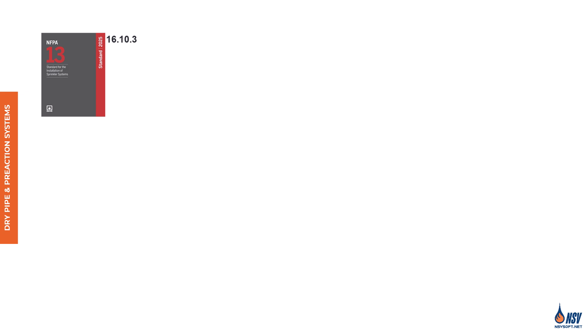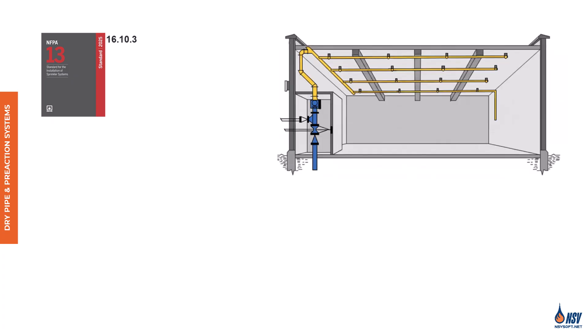Section 16.10.3 of NFPA 13, 2025, outlines the pipe pitch requirements for dry pipe and pre-action sprinkler systems. Proper drainage is essential, especially in areas subject to freezing, to prevent water from accumulating and causing damage. Because these systems are often installed in environments prone to freezing, proper drainage is critical. Water trapped in the pipes can freeze within minutes in areas maintained at or below 40 degrees Fahrenheit. Additionally, stagnant water can lead to internal pipe corrosion and calcium buildup, which may obstruct sprinkler heads during a fire.